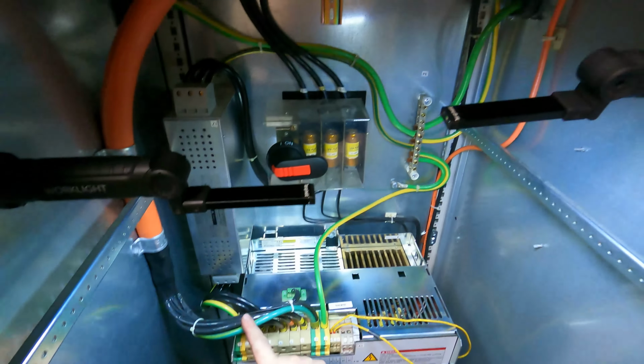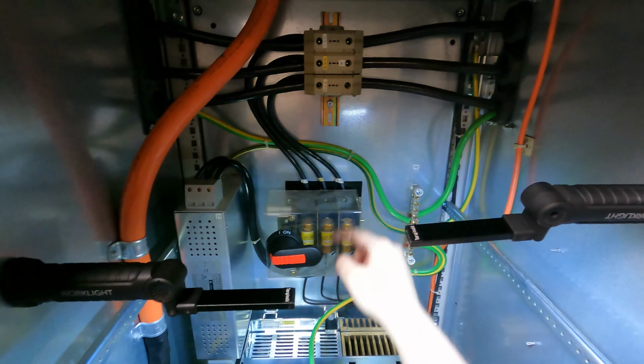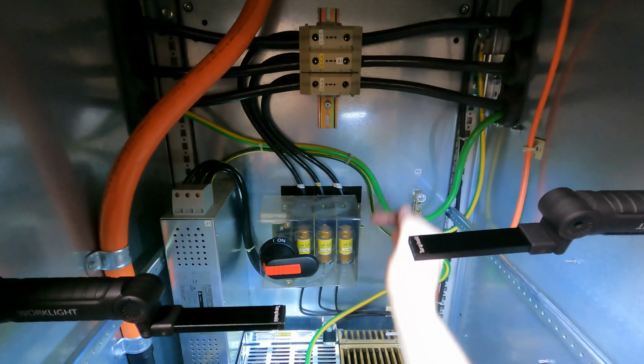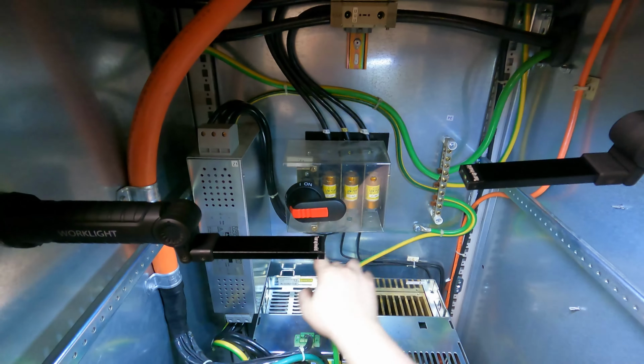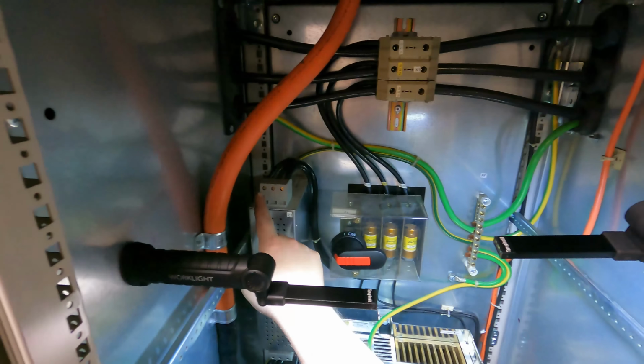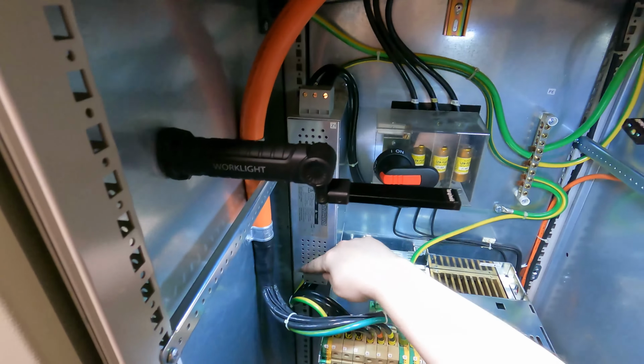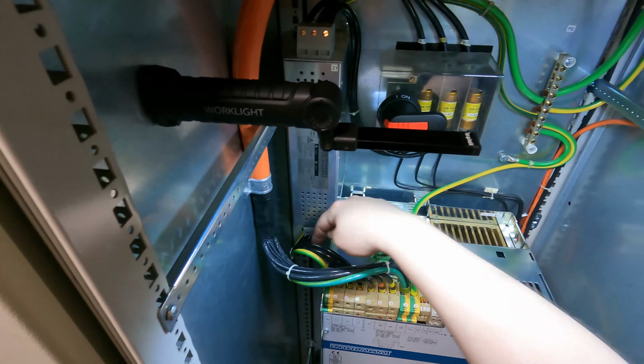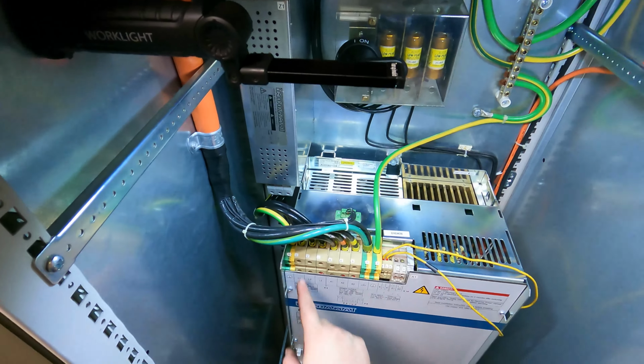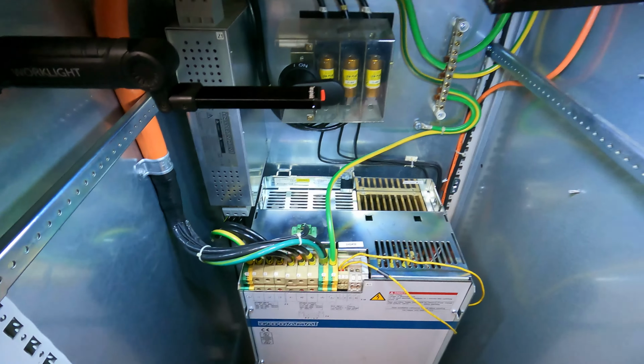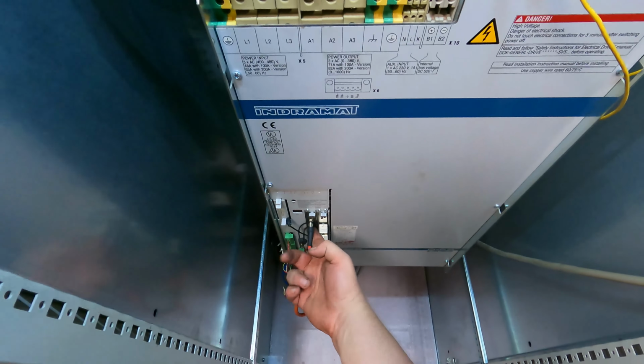But if you ever don't know if you have the phases right, you can just follow it in here. You can see at the top, it says line 1, line 2, line 3. It's coming out the bottom the same way, so you just trace the wire around. Line 1, 2, 3. So you just follow the wire, 1, 2, 3. And then A1 through 3 is to the motor. So last check, just make sure everything is seated properly.